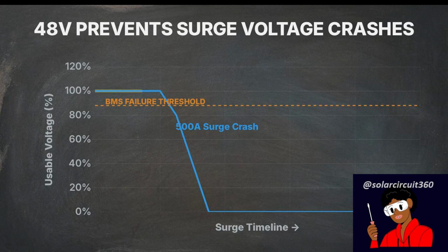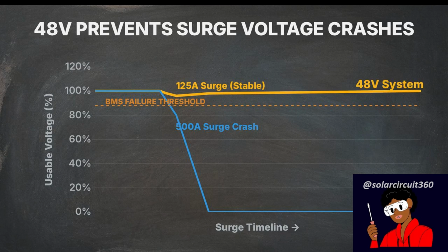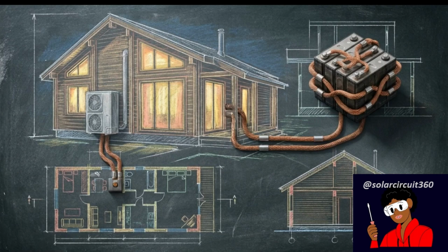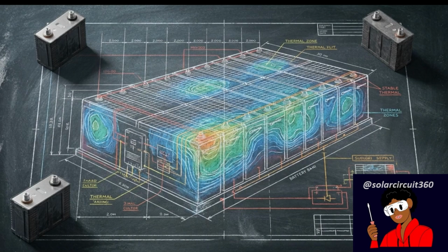The 48-volt system avoids this entirely. Because its surge amperage is a fraction of the size, the voltage drop is strictly suppressed. By maintaining extreme stability during heavy load spikes, high-voltage architectures allow you to actually utilize the full capacity you paid for without random system reboots. Professional engineers design off-grid systems around 48 volts to carefully control the thermodynamic stress environment, not to save money on copper.